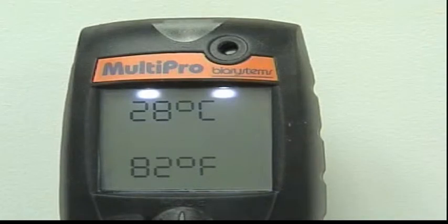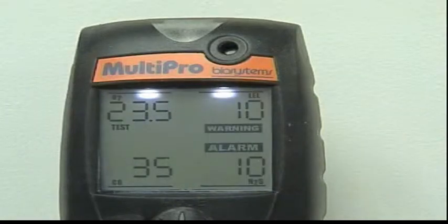After the self-test, the temperature currently registered by the instrument will then be shown. Note that the temperature shown is the temperature in the MultiPro's sensor chamber and may not correspond to the ambient air temperature. The next 4 screens displayed by the instrument are the alarm screens. The first alarm screen is the warning alarms. Warning alarms indicate a hazardous atmospheric condition that has not yet risen to the level necessary to initiate the danger alarms. The warning alarm is indicated by a repeating single-tone audible alarm.